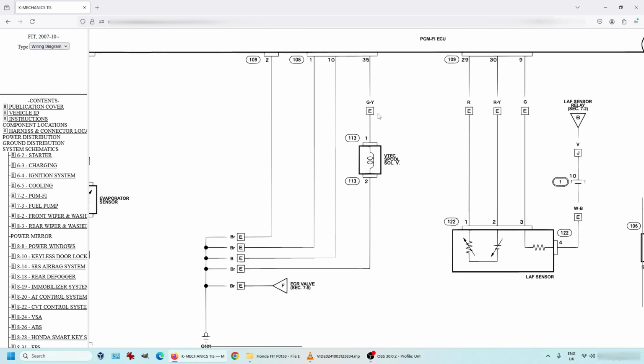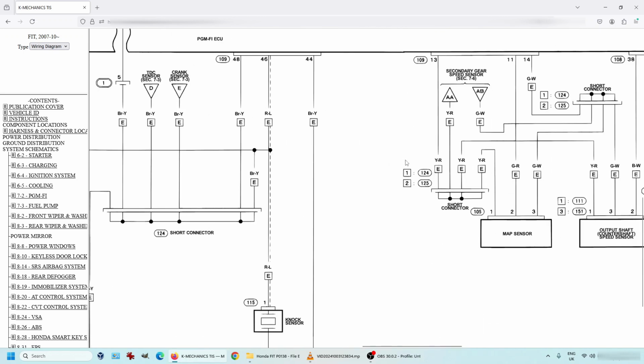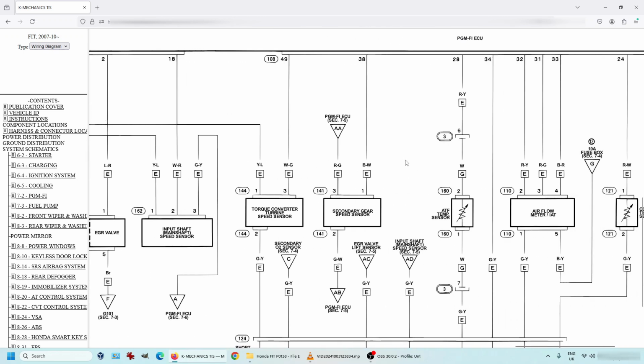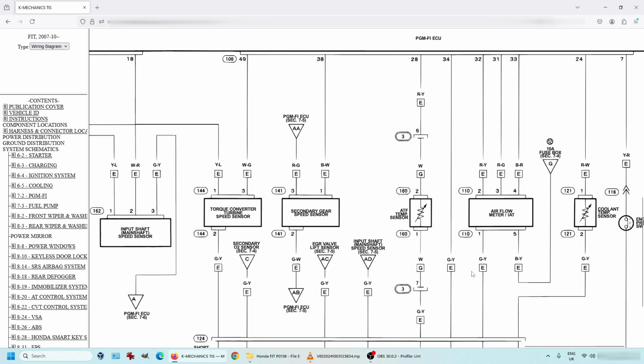So the repair is very simple. We're going to remove that line from this green yellow wire of pin 35, and we put it on this green yellow wire, which is pin 34 of the same connector 108. That should solve our issue of high voltage, because the sensor ground will remain a ground all the time.